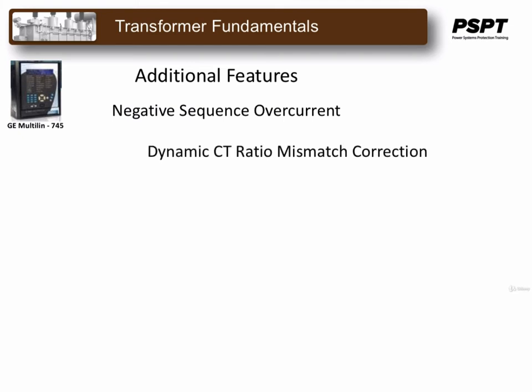Dynamic CT ratio mismatch correction accounts for various variations in on-load tap changer positions. Tap positions are monitored and CT ratios are corrected accordingly automatically. For over and under frequency protection, the 745 calculates and maintains a running average of the system frequency and the frequency rate of change. 2 under frequency and 4 rate of change elements are provided to implement traditional and advanced load shedding schemes. Additionally, an over frequency element can be used to trigger a generator ramp down.